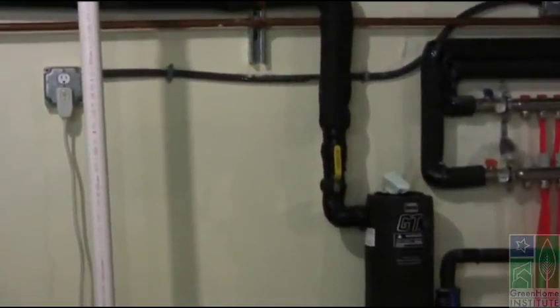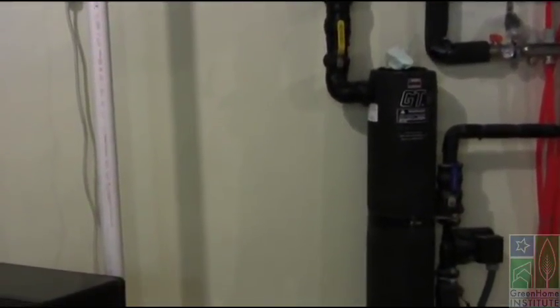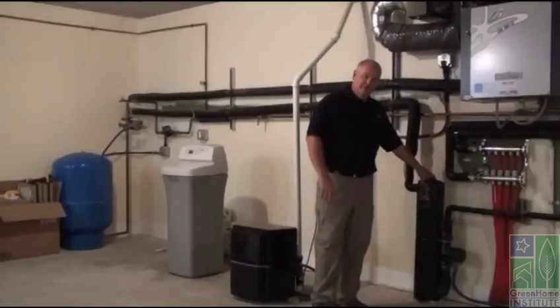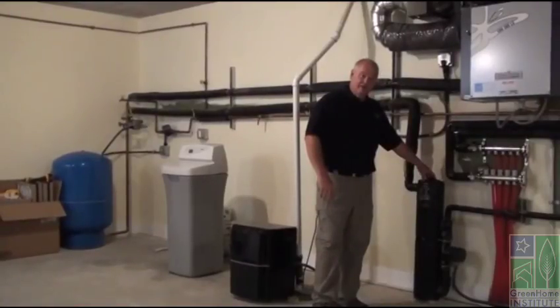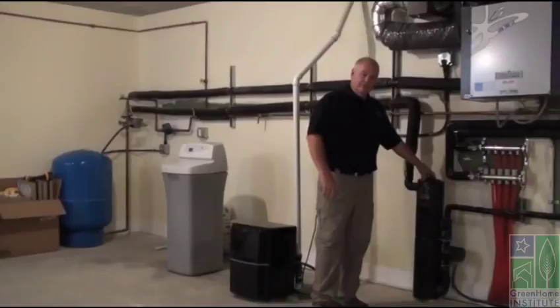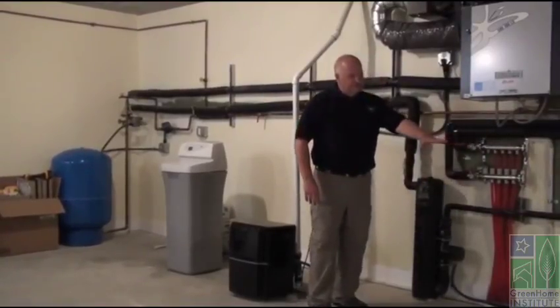It stops in here at this contraption, which is an air separator. So occasionally you'll get bubbles that are in the line when they install it. And this allows those bubbles to be separated out. And from there it goes into the geothermal heat pump.